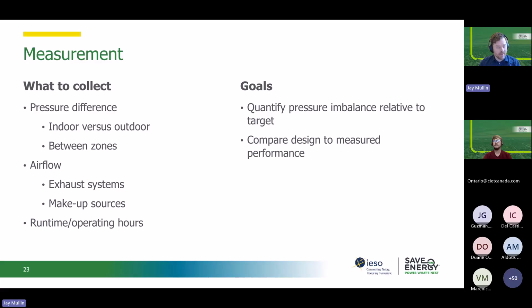You also want to collect data on airflow. So what is the airflow that the exhaust systems are ejecting from the makeup sources, and then collecting data on actual runtime and operating hours. So when is the equipment running? How does that line up with production, with operations as well? And the goals of the measurements here are really to quantify that pressure imbalance relative to the target, whether it's intentional or just looking at that slightly positive, and then to compare design.